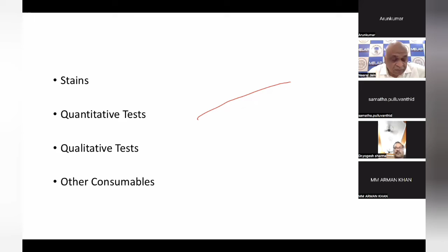Now, for quantitative tests, like your hematological parameters, CBC parameters, or biochemistry tests, hormones, what is required? You are running controls otherwise, and you are checking whether these are within 2 standard deviation or not, from +2 to -2. For a new reagent kit also, you follow the same principle, because whenever there is a change in the reagent, patient samples shall not show significant variation, and a control is also like a sample only. So you can use the same principle. Yes, it is not showing significant variation.